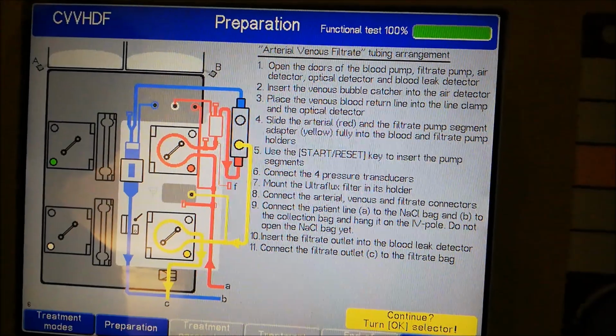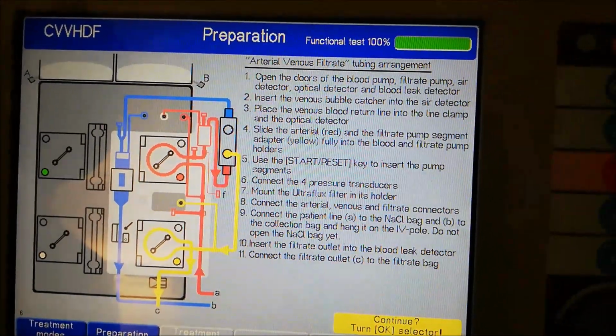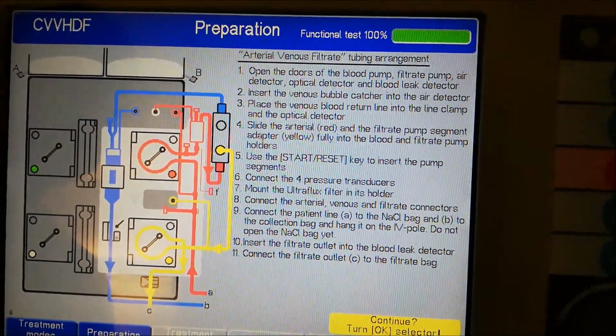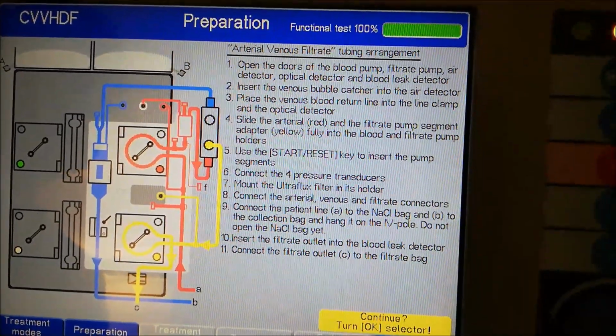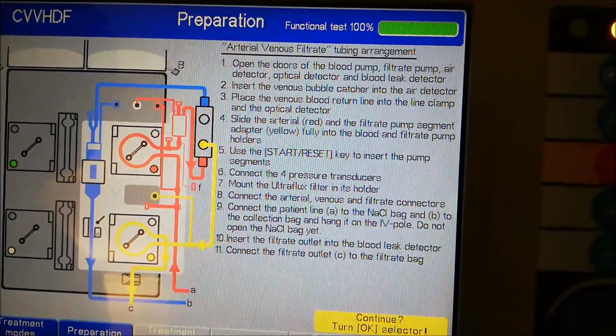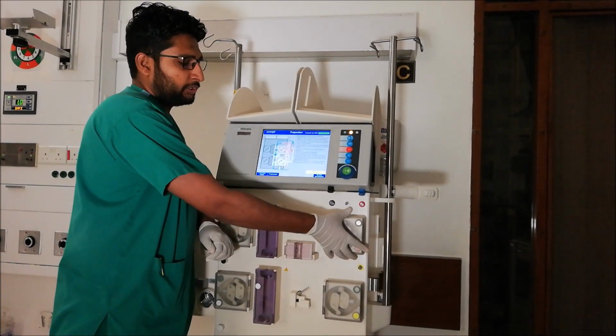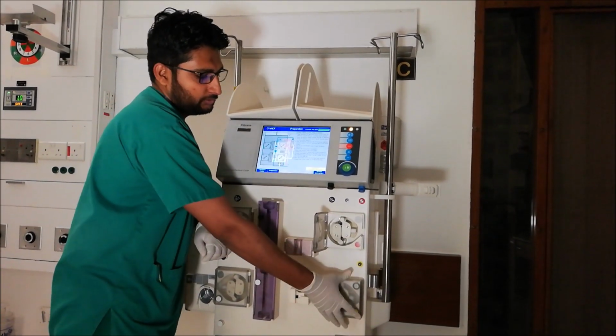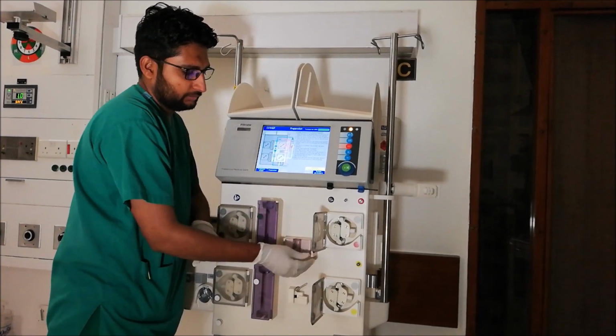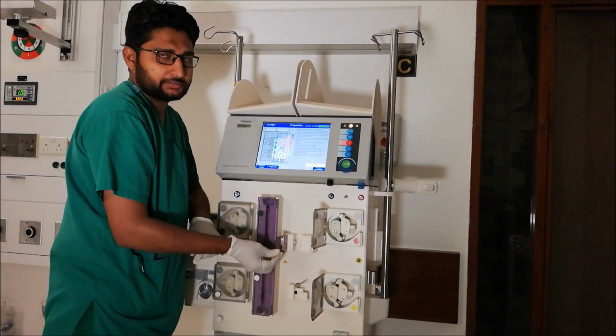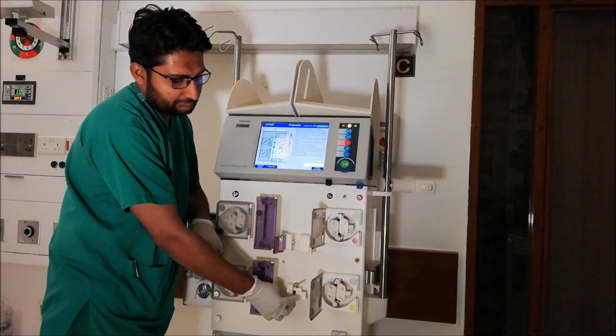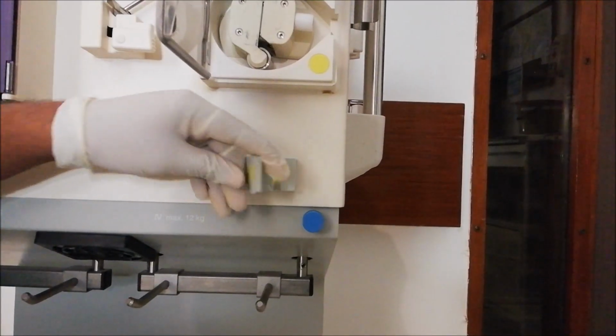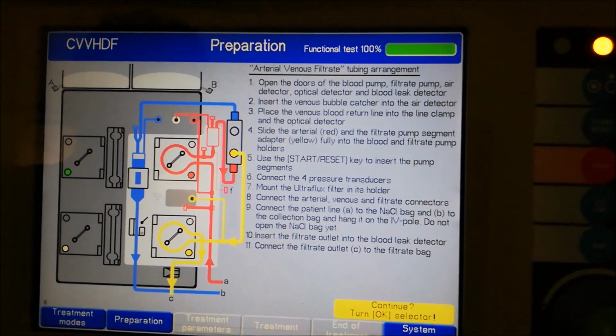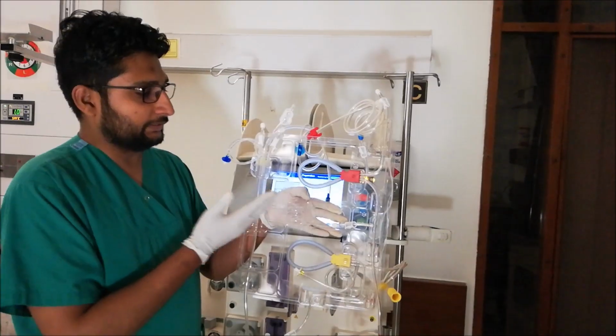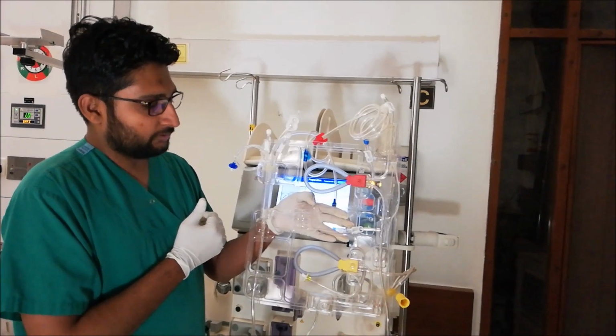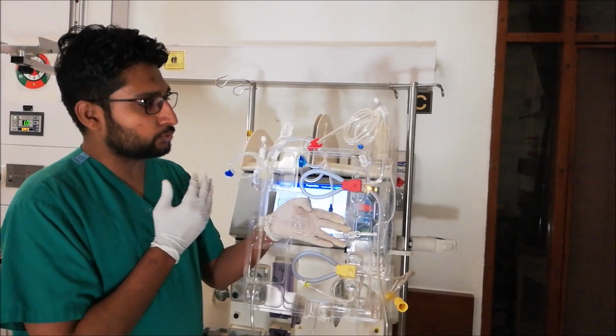Our first step is open the door of blood pump, filtrate pump, air detector, optical detector, and blood leak detector. Open the door of blood pump, filtrate pump, blood leak detector, optical detector, and blood leak detector. Insert the venous bubble catcher into the air detector. This is an installation kit for multi-filtrate machine. It is also color coded.